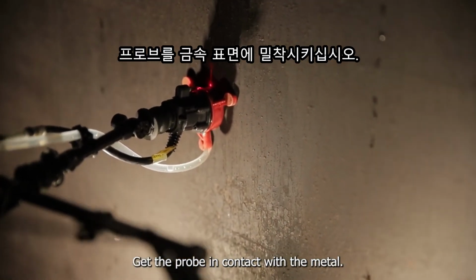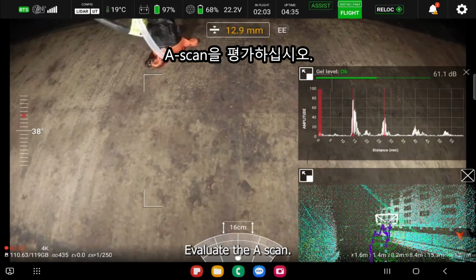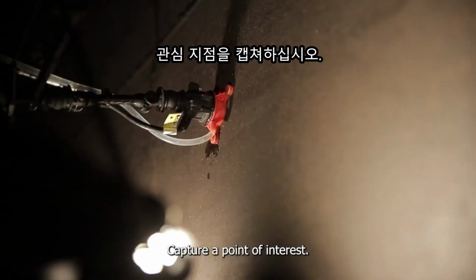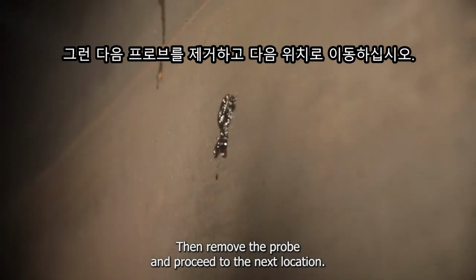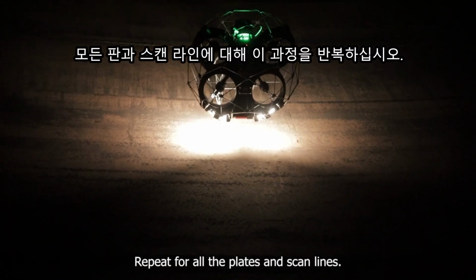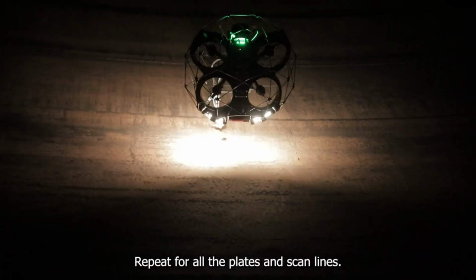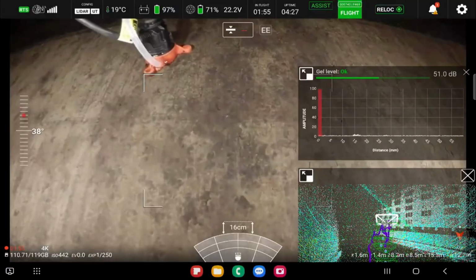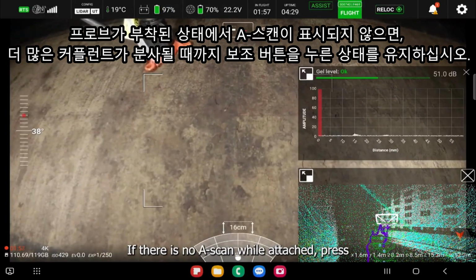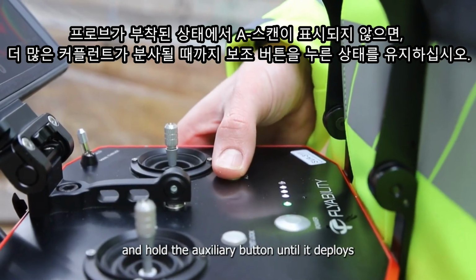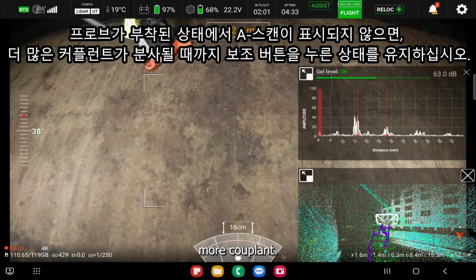Get the probe in contact with the metal. Evaluate the A scan, capture a point of interest, then remove the probe and proceed to the next location. Repeat for all the plates and scan lines. If there is no A scan while attached, press and hold the auxiliary button until it deploys more couplant.